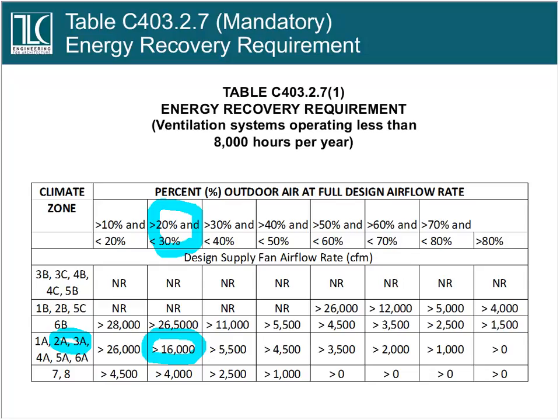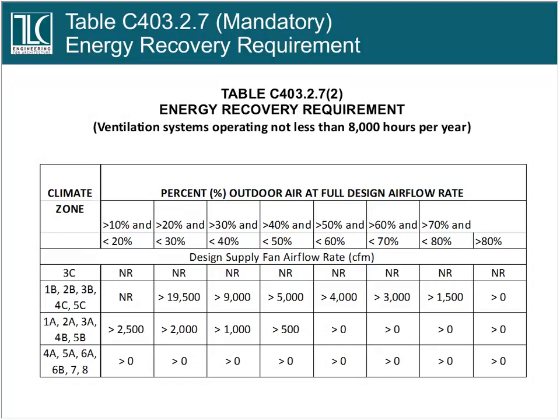The energy recovery equipment that goes with a box that's about 6 feet square is another box about 6 feet square. So you're either going to be putting in a lot of smaller systems to get away with not having to put in energy recovery, or you're going to have to increase the mechanical equipment spaces in order to accommodate that. If you have a 24/7 operation that's operating at more than 8,000 hours per year, those size requirements have gotten really small. So basically, anything bigger than a big fan coil unit is going to have energy recovery on it. And this is not that much outside air. So once again, stuff that we've not had to do in the past is now mandatory.